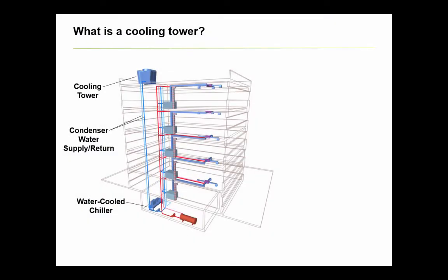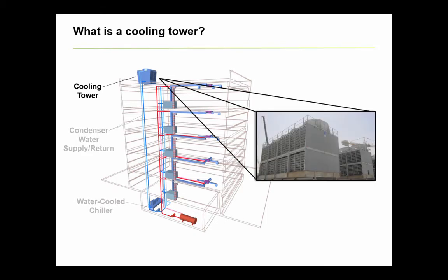So what is a cooling tower? Well, as you can see from the image, a cooling tower is used in water-cooled chiller plants, and its purpose is to reject facility heat to the atmosphere. The air handling unit and chiller tandem absorbs the building's heat and ultimately passes it to the cooling tower via the condenser water loop, which then transfers it to the ambient environment.